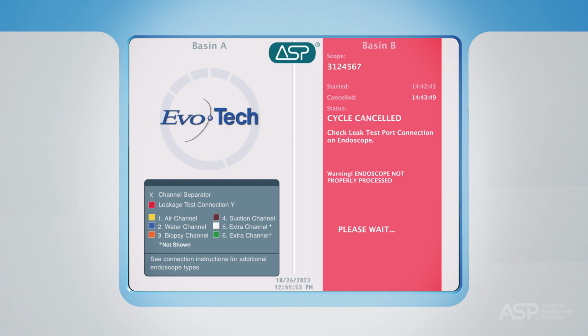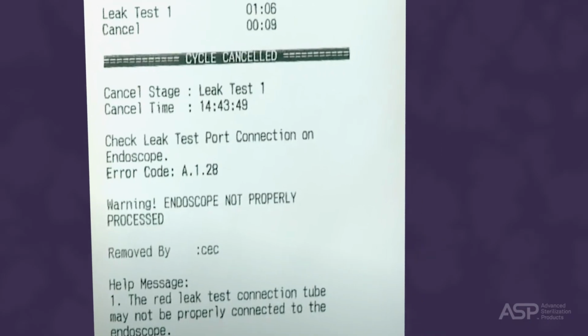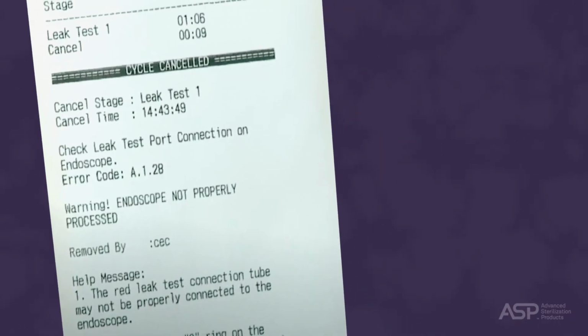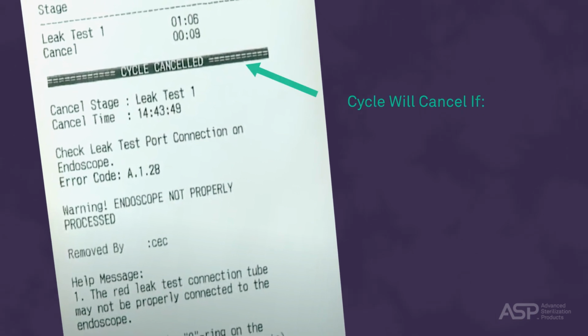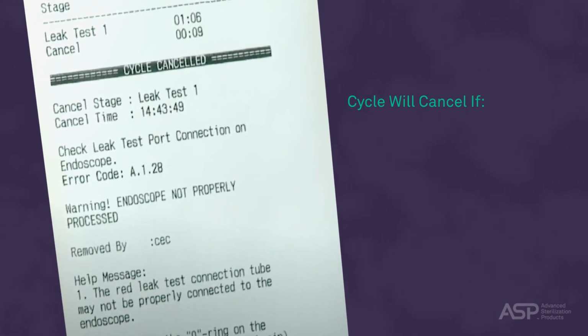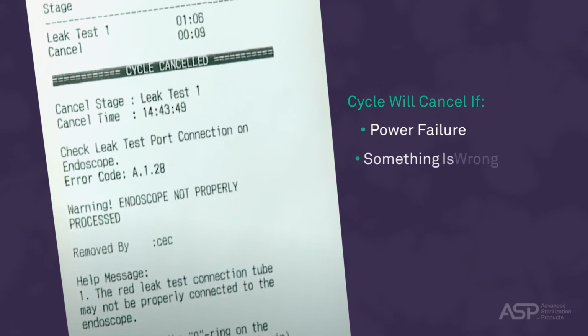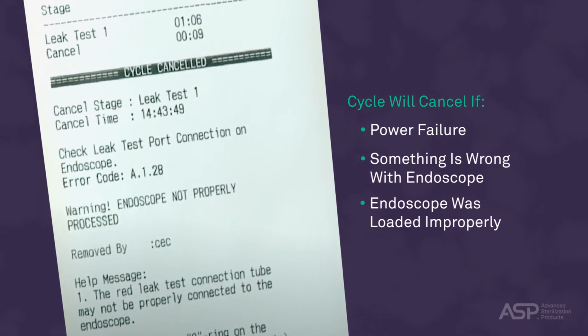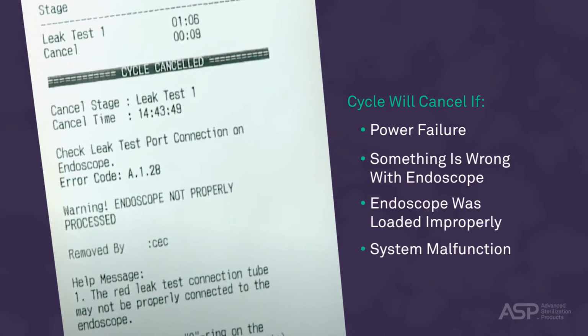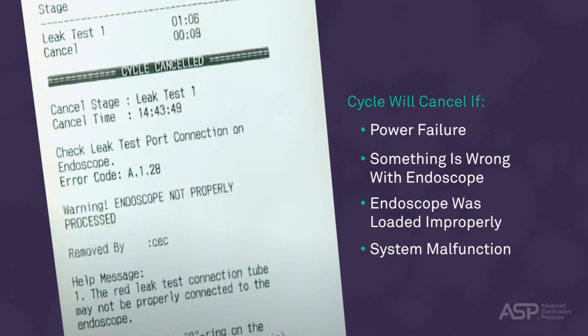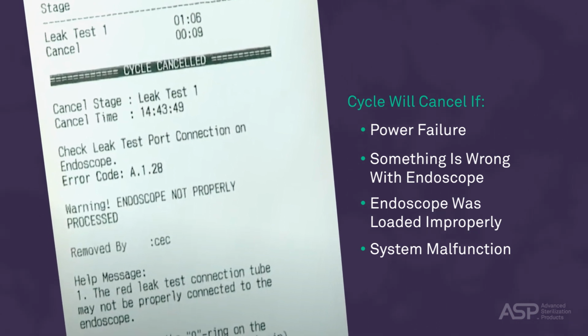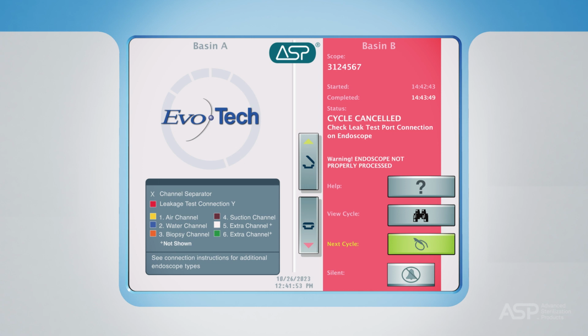If the cycle cancels, the touchscreen will be red and an alarm will sound. The reason for the cancellation will be displayed on the printout. Cancellations may occur because you touched cancel during a cycle, there was a power failure, there was something wrong with the endoscope or the way it was loaded, or the system has malfunctioned in some way. The message will direct you to which action to take if a cycle cancels. You may also touch the Help button for more information.